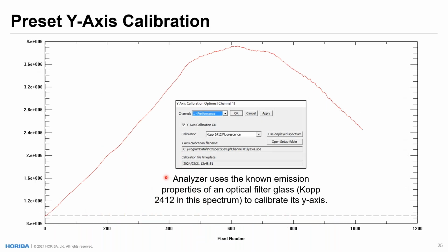Likewise, with the y-axis calibration, so intensity normalizations here, our analyzers come with a preset y-axis calibration based on the Raman probes that are interfaced to your analyzer. So here in Salt Lake City or at your site, we calibrate the y-axis of the analyzer, and this calibration is only done once per probe that the analyzer collects on, and then is installed for all subsequent measurements using that Raman probe. So this is something that usually only needs to be done once per probe when it first starts.